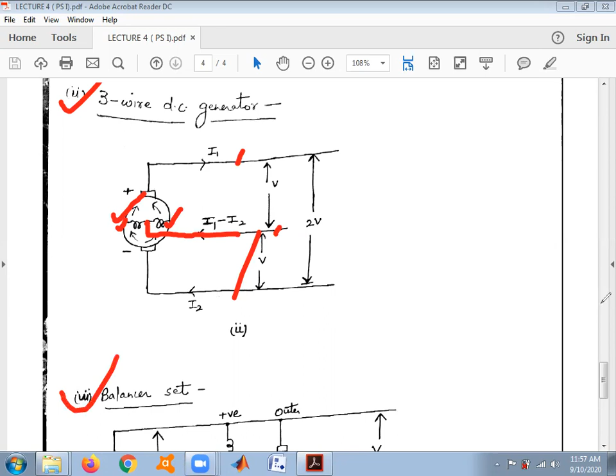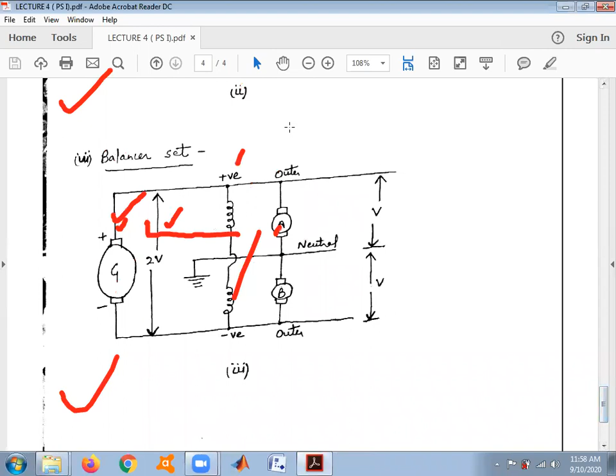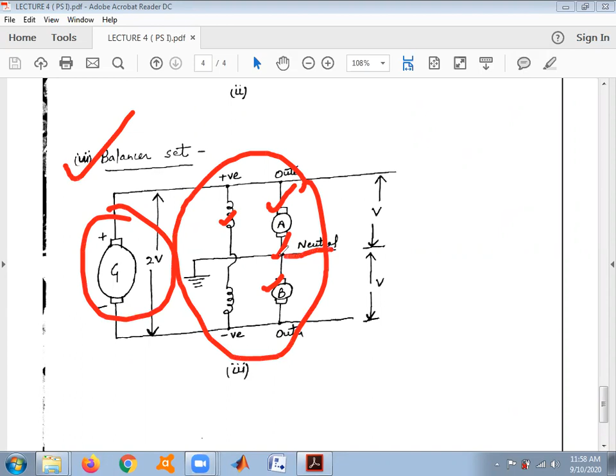The third method we use for the three wire system is the balancer set. In this method, a single generator is used and the balancer set is connected across this generator. Two identical DC machines are used and their armature and field windings are connected in series, as shown. From the middle point of these windings, the neutral is taken out so that the voltage between the outer wires is 2V and between the outer wire and neutral is V. The main advantage of this method is that it maintains the potential difference constant between the outers as compared to the other methods.